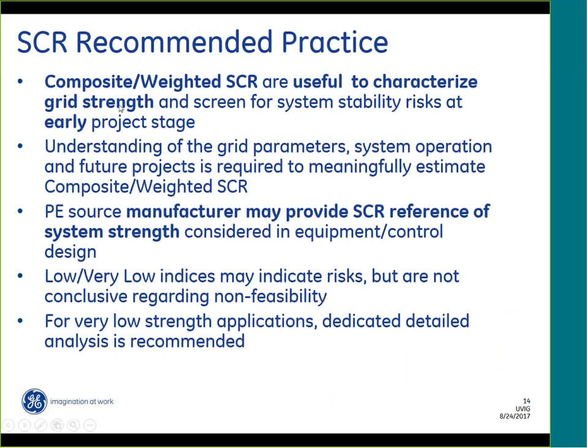The advantage that this has is that it allows for a simple calculation that characterizes system strength, and you can do this early in a project. You don't need to have all the details defined in a project to estimate or approximate system strength. It's an advantage of it.